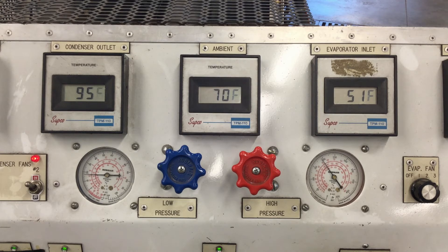The low side pressure looks like it's just a little bit under 20 — about 18 PSI — and it's kind of dropping just a little bit. What we're seeing right now is a normal TXV system, and we're letting it stabilize to show what a normal system would look like.